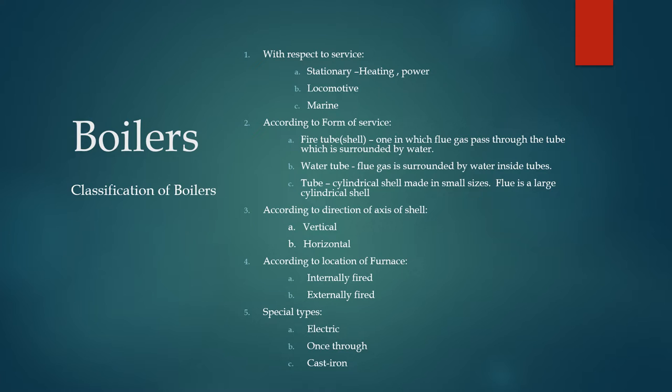In water tube boilers, water is inside the tube and flue gas surrounds it. The tube is a small cylindrical shell, whereas the flue is a large cylindrical shell — that is the difference between a tube and a flue. The third category is according to the direction of the axis of the shell — whether it is vertically mounted or horizontal. The fourth is according to the location of the furnace — whether it is internally fired or externally fired.